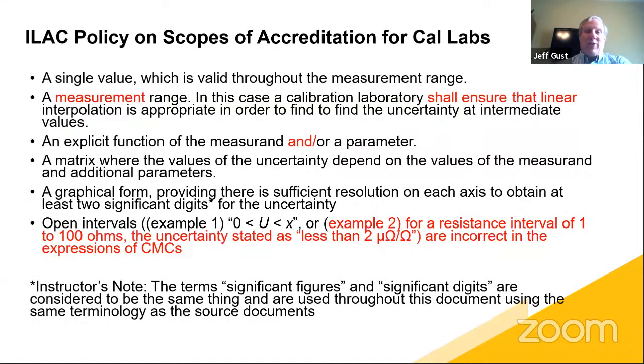You could do it in a graphical form, so long as you have enough resolution on that graph to understand the uncertainty to 2 significant digits that you're providing for the customer. I have seen some graphical forms before. For example, network analyzers quite often provide a frequency sweep and provide the uncertainty in a graphical form. But again, you need to have sufficient resolution out of that as well.